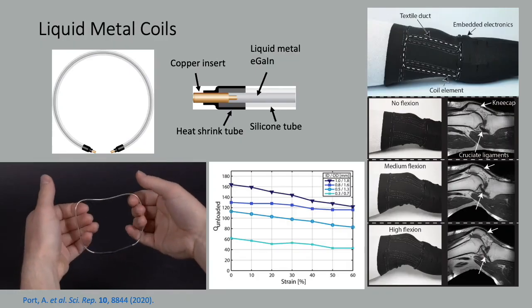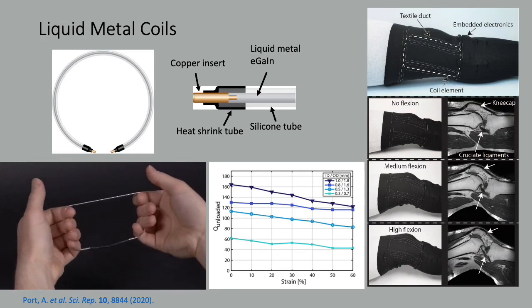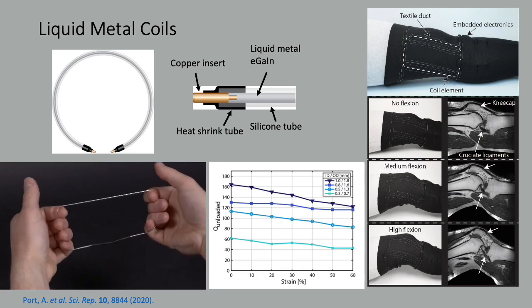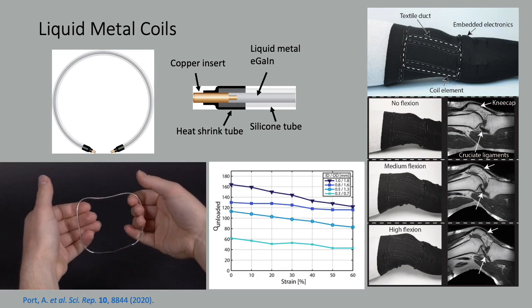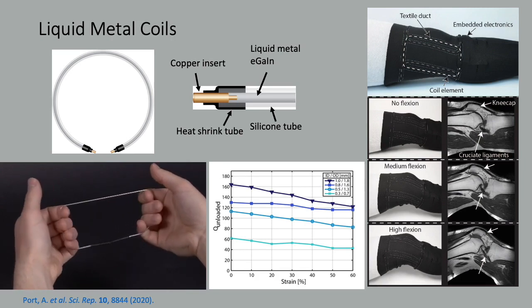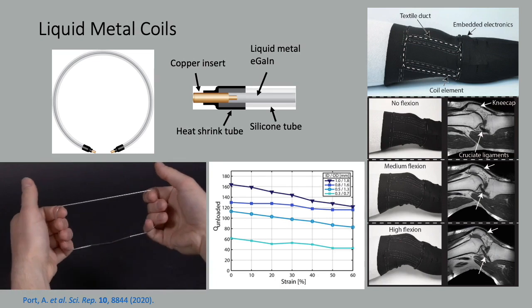This is from the ETH Zurich group. They introduce a novel, non-toxic liquid metal encapsulated in a silicone tube to enable the elements to flex. Interface is done through a copper insert, and the coil elements are integrated in flexible textile. The conductivity of gallium-indium is, of course, less than copper, but is still high enough to achieve body noise dominance.